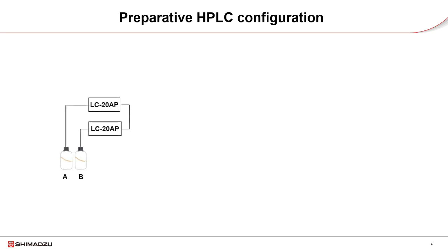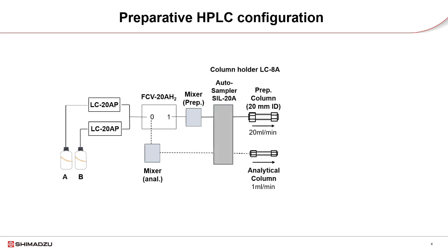The general process of a preparative HPLC system begins with the mobile phase flowing through a solvent delivery system, which includes high-pressure pumps. Along this path, the solvent will pass through a mixer, where it is thoroughly mixed as required for the chromatographic separation. Next, the eluent is introduced into the chromatographic system through either an autosampler or a manual injector, facilitating the introduction of sample aliquots into the mobile phase stream.